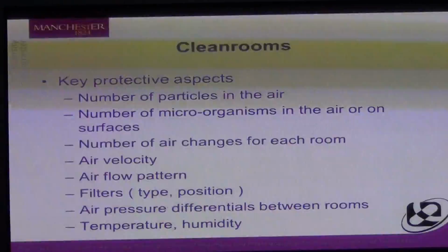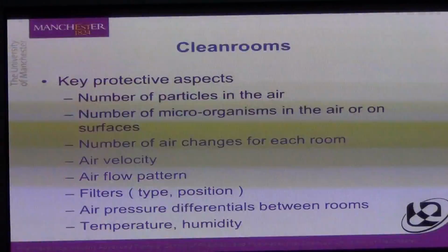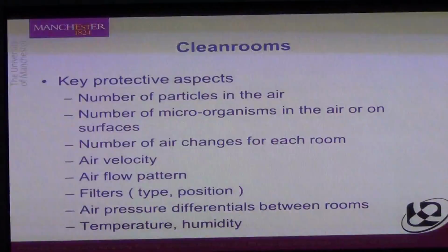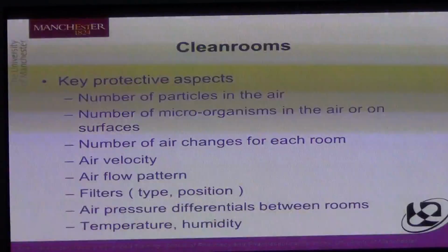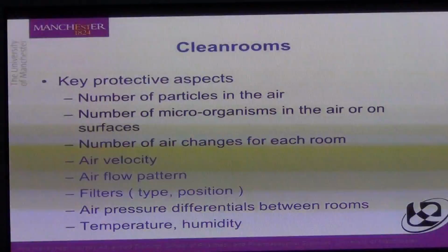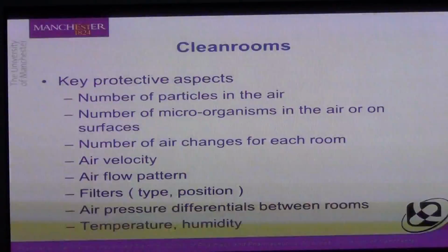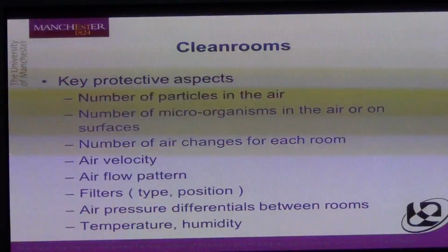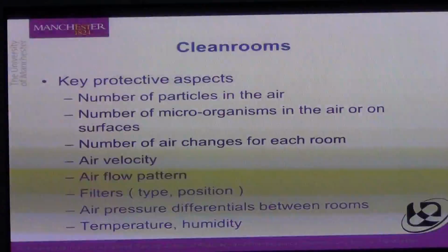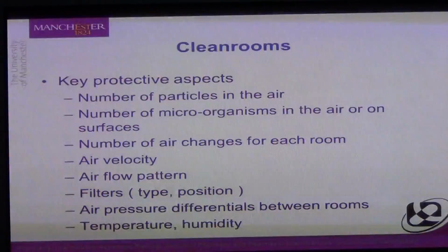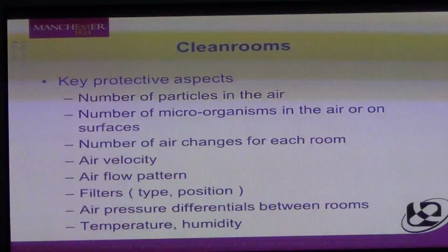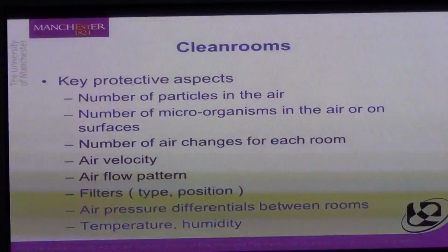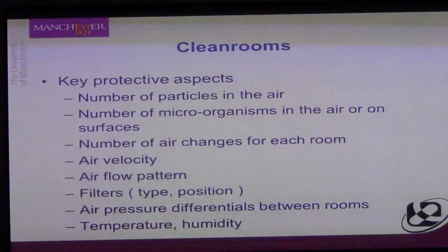So the protective aspects of clean rooms are that we control the number of particles in the air, and we control the number of microorganisms in the air, or those that might land on surfaces. We make sure that the room is regularly supplied with clean air being pumped in, and this is assessed by counting the number of air changes per hour. A modern design clean room would have something well in excess of 20 air changes per hour, more likely over 40 air changes per hour.